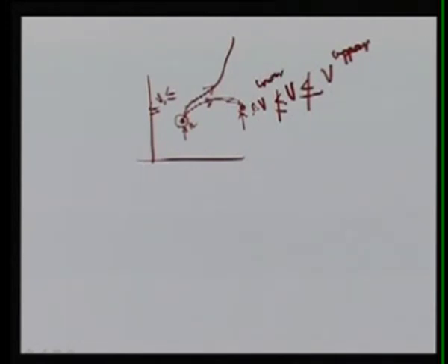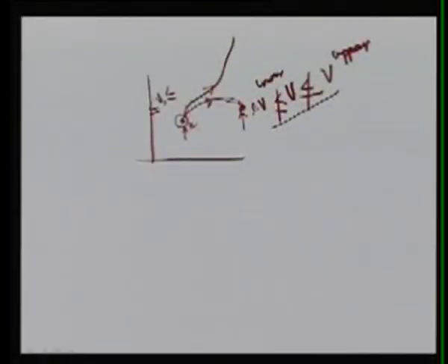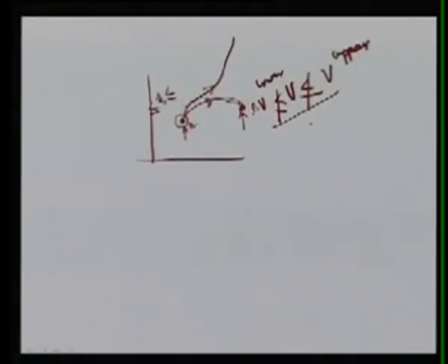So, the system is stable, but it is violating the operating constraints. In this case, I have taken the voltage, but it may be your line flows overloading, or violation of reactive power limits, and so on. This point is stable, this point is stable, so in terms of stability our system is stable, but in terms of security, these points are stable yet the system is not secure. So it is one step ahead, where we have to check that operating limits are well within limit. That is your power system security.